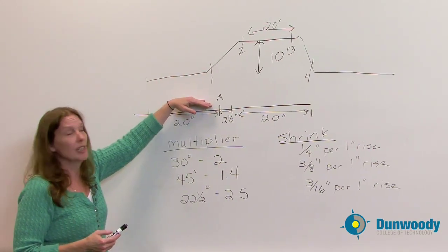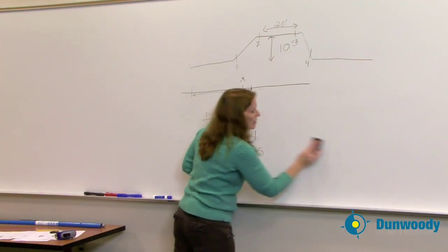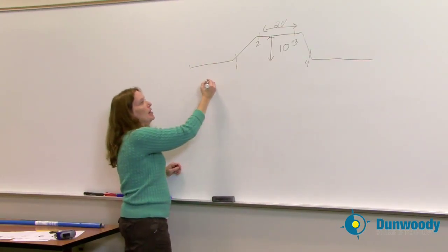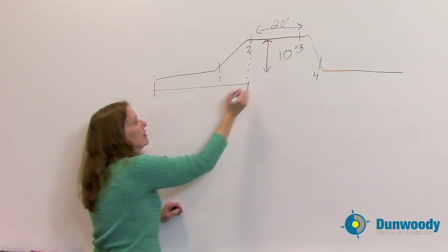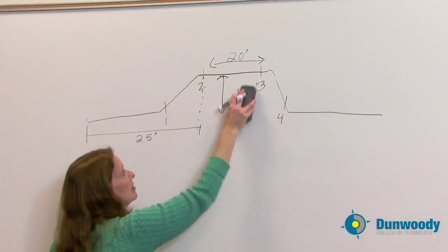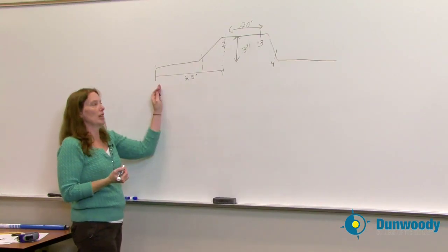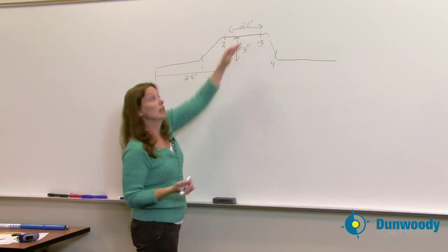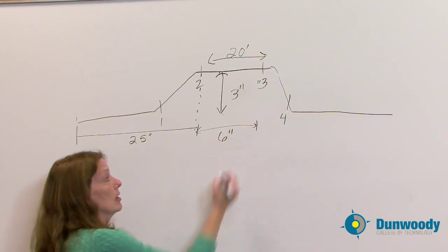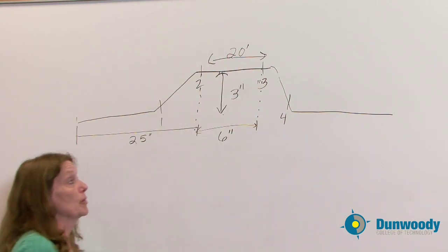So how do we begin a four-bend saddle? It's basically two back-to-back offsets. Let's look at a problem: I have an obstruction, and from this side to this point is 25 inches. The obstruction is three inches tall and six inches in length. I want to bend that conduit around that three-by-six-inch obstruction.